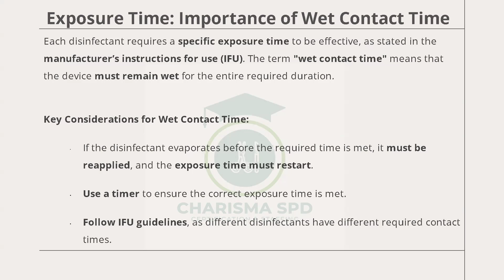We had a mock survey. As a matter of fact, there is a hospital, Queens, that had a mock survey before I went there. One of the findings was that they didn't have a timer. The Joint Commission, there is a body we call the Joint Commission, prefers that you have a timer where you set it, because you can forget. Overexposure can lead to damage. So if it is 5 minutes, 5 minutes. It shouldn't be 10 minutes. If it is 10 hours, it should not change to 11 hours. So a timer is very, very important. Then the IFU, follow the IFU as it says. Thank you. Next slide, please.